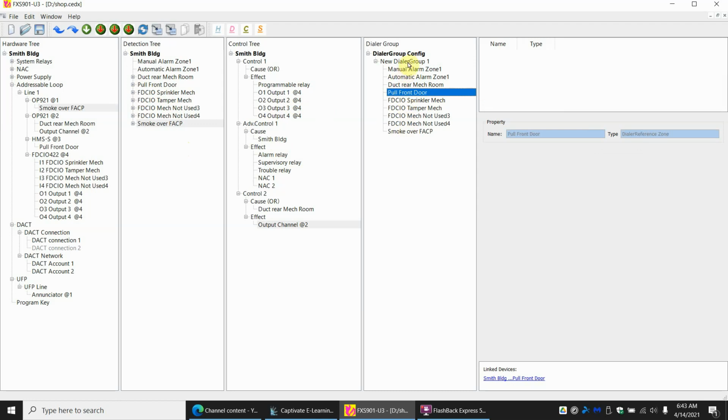Therefore, what do you tell monitoring to report zone 1 as? Fire alarm has been triggered somehow. That's not useful at all. So what we have to do is count how many zones we have here. 1, 2, 3, 4, 5, 6, 7. Which technically 2 of them are not used. So actually only 5. You already have 1. We need 5, so we're going to add 4 more.